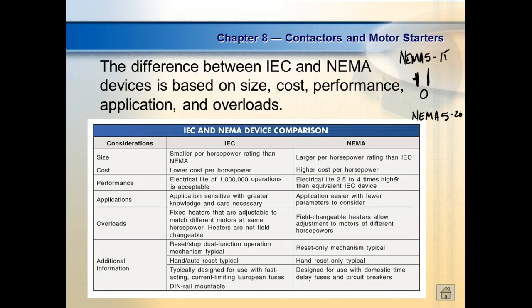So every plug that we use in our house is a standardized plug. If it's not a standardized plug, that means I would have to buy that plug from the manufacturer. I couldn't go to Lowe's and buy one, right? So you go down and start looking on Lowe's electrical aisle and look at all those different plugs, and every one of them is going to have a NEMA number. Oh, all your 240 plugs are standard. Of course, they're different. Unfortunately, they're different 240 plugs.